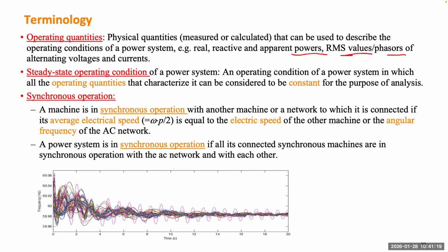Okay, this is one example after a disturbance, and each curve represents a synchronous generator's electric speed or frequency in hertz. So the center frequency is 60 hertz, right? So it starts from 60 hertz. After some disturbance, finally all generators will have a frequency pretty close to 60, not exactly 60. So it will slightly go down. Probably this event is just a loss of a single generator, and the frequency declined a little bit, but still very close to 60, probably 59.99 hertz. And we see all the generators are actually in synchronous operation, and this power system is in synchronous operation.